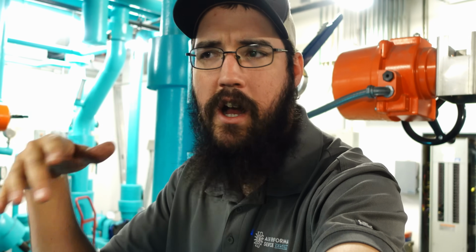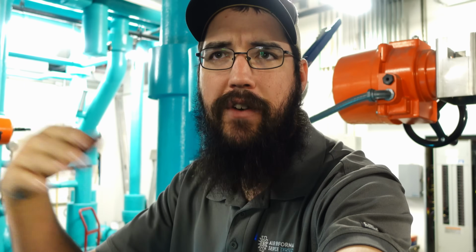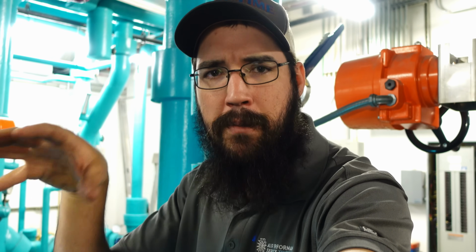And so on a smaller system, their 37 PSI rating might make more sense. And you might see it actually increase when you get down to that upper 30s range. But when you're working on a centrifugal or a larger system like this, in that 30s range there's still a lot of volume, even though it's a lower pressure. So we're going to be doing some testing, and this is something that I want to work on. I'm going to try to see if I can find a better sweet spot, and maybe it's something more specific to the heavy commercial side. If you're doing, say, smaller RTUs, it would mean a lot less to you. But a more accurate number might be something like 20 or 25 PSI on that final recovery.